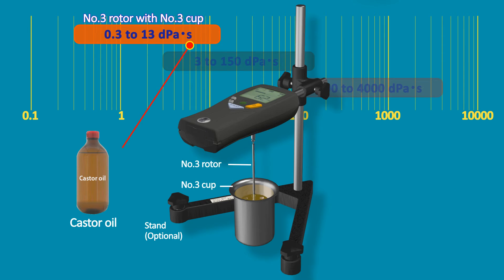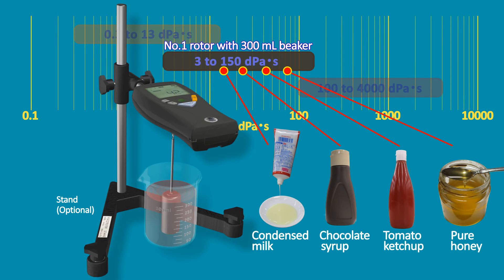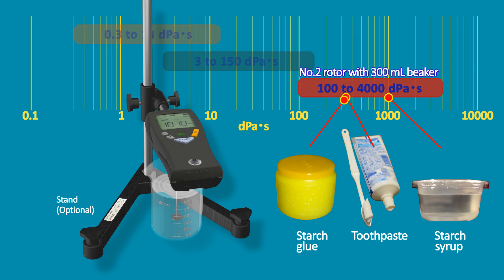The number 3 rotor with the number 3 cup covers 0.3 to 13 dPa·s fluids. The number 1 rotor with the JIS 300ml beaker covers 3 to 150 dPa·s fluids. The number 2 rotor with the JIS 300ml beaker covers 100 to 4,000 dPa·s fluids.